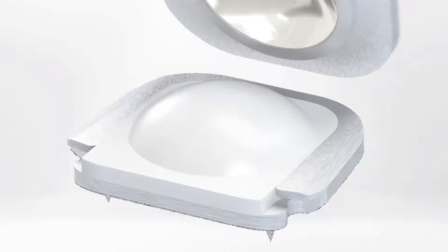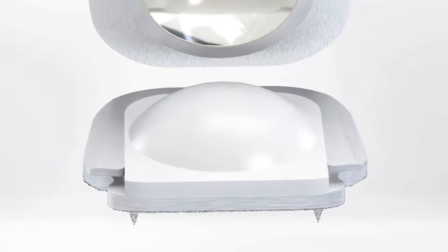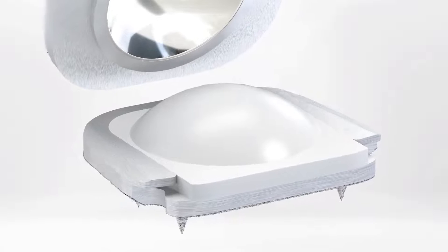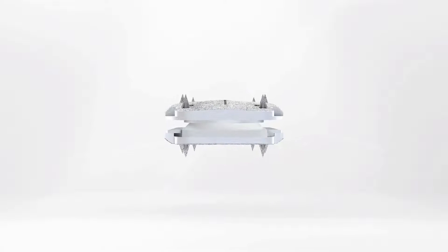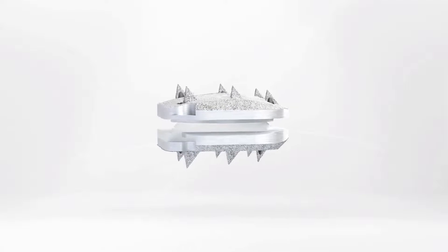ProDisc-C Vivo is composed of two cobalt chrome alloy end plates and a polyethylene insert. The polyethylene insert is affixed to the bottom end plate, forming the ball, and a polished dome in the top end plate forms the socket.